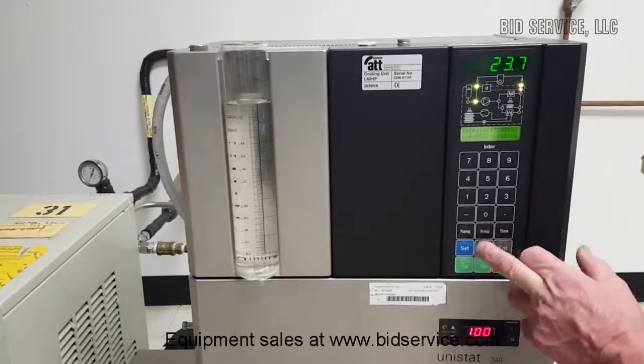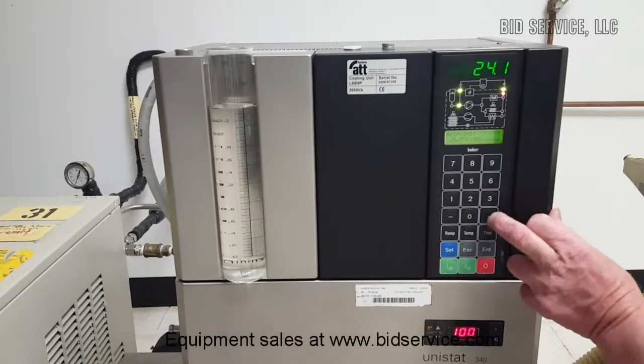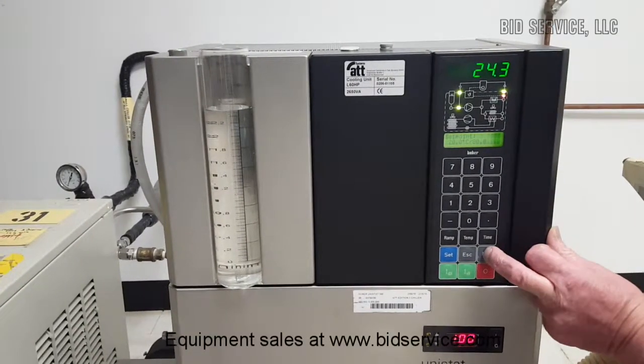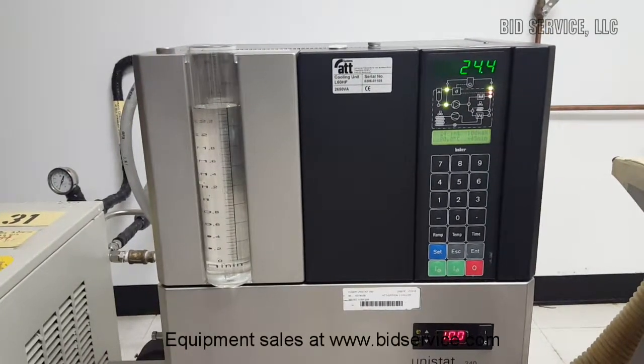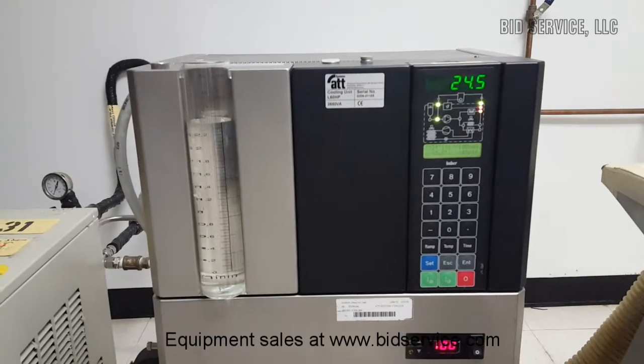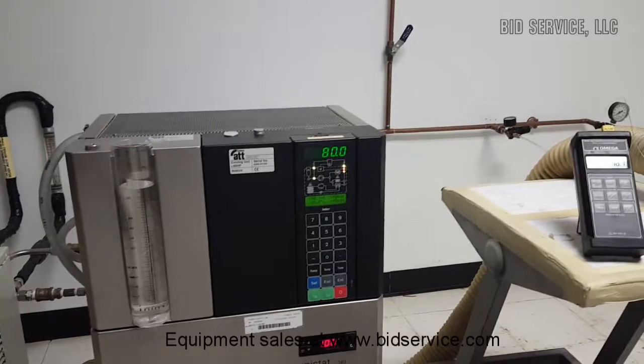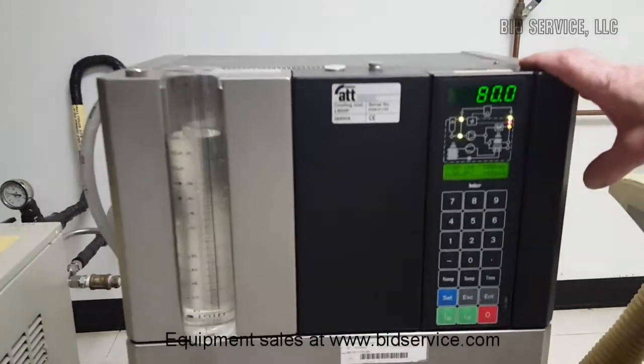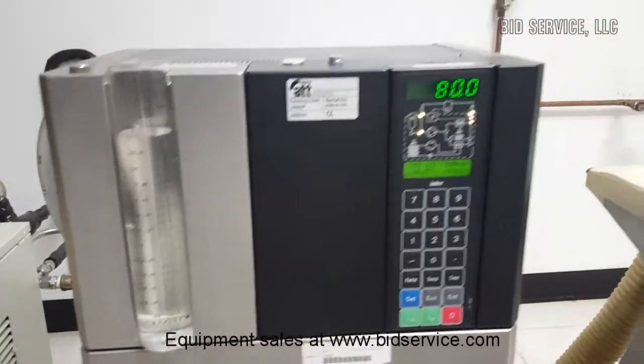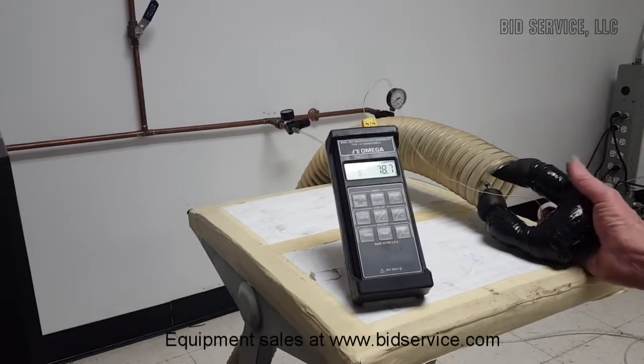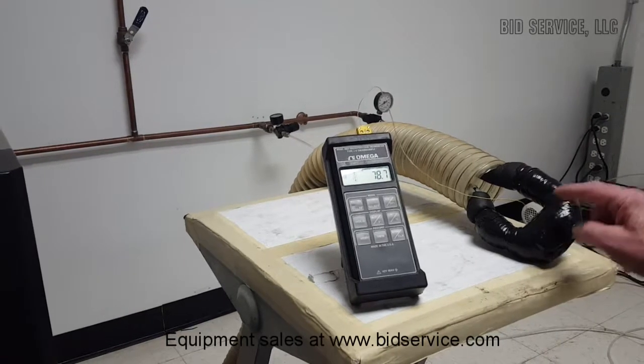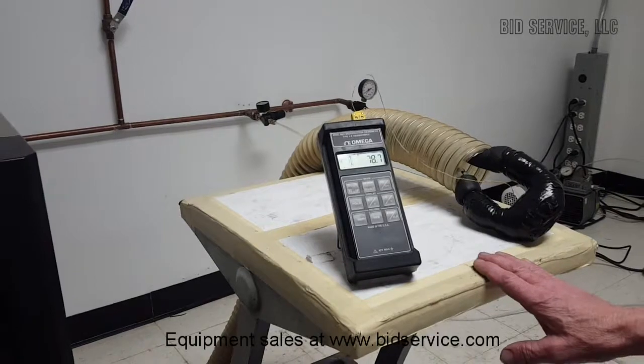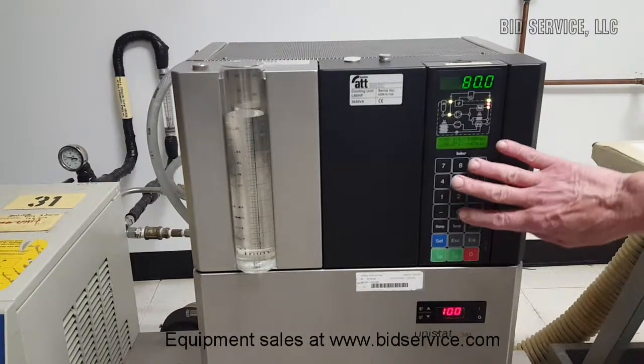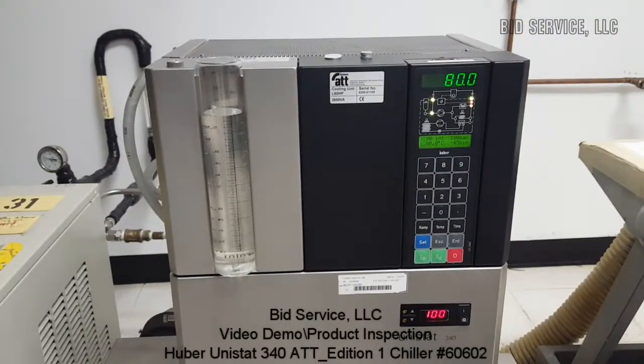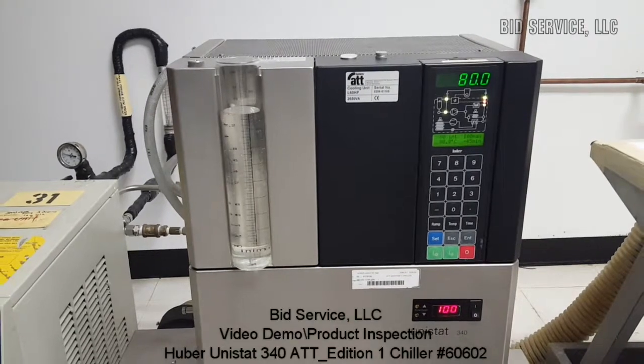What we'll do is we'll change the temperature for this part of our demonstration to plus 80 degrees C, which is the equivalent of 176 degrees Fahrenheit. And now we'll heat up the system. We'll come back in a little bit and see how it's doing. Okay, we've now come up to about 80 degrees C. This again is testing with water. We're measuring right at the end where your cold trap or your application would be, and it's measuring through the thick stainless steel wall, and that's about 1.3 degrees difference, so that's pretty good. Other than that, once you read the manual, you'll find this is very easy to set up in automatic or manual, and it's very reliable and extremely precise. This completes this demonstration.